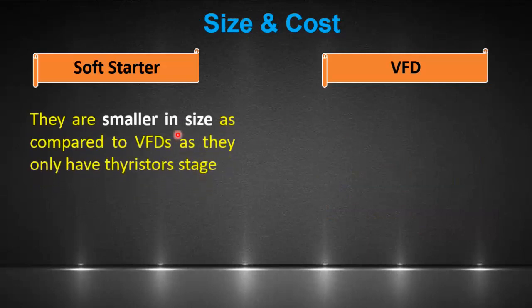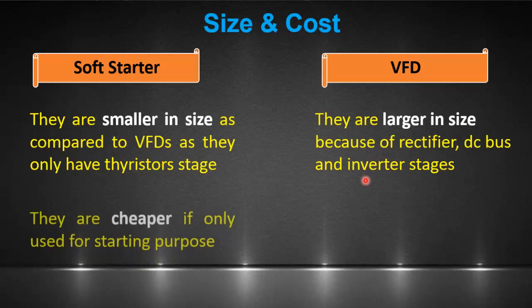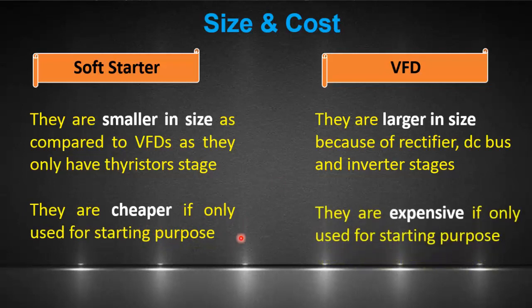The size of soft starters is considerably smaller compared to VFDs because they have only a thyristor stage, whereas VFDs are larger in size because of the rectifier, DC bus, and inverter stages. Because of this simpler hardware, soft starters are cheaper in cost. If a VFD is used only for starting purposes, then it is the more costly option.